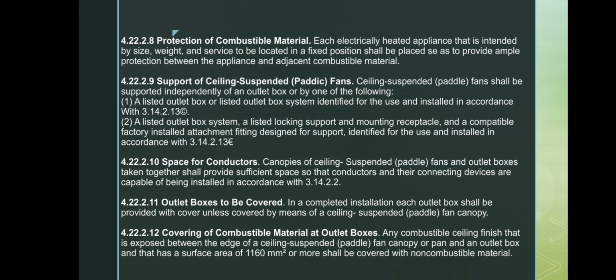Ceiling suspended or paddle fans must be supported properly. They should either be mounted independently of the outlet box or attached using a listed outlet box or support system designed specifically for fan installations. The fan canopy and outlet box must also provide enough space for the conductors and their connectors so they can be installed safely.